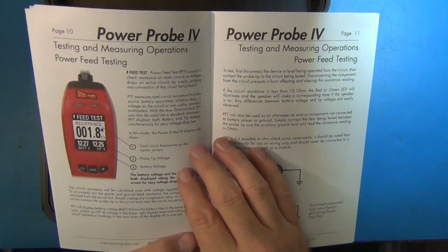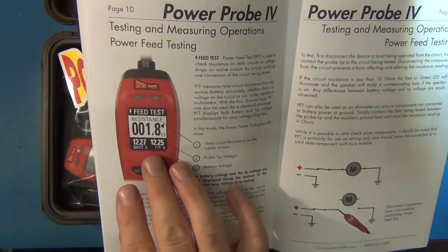The feed test shows you whether or not you have a good power source. It'll tell you the resistance of the circuit you're on, and the battery and tip voltage. The battery voltage and tip voltage can't be off by about half a volt, or it'll say something's wrong. It'll show you the resistance of the line, so you might be getting voltage, say 12 point some volts, but if that's got high resistance, you'll know the circuit's no good.